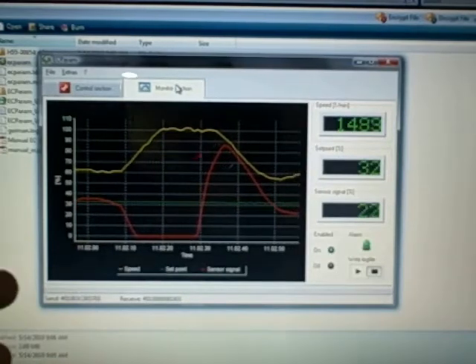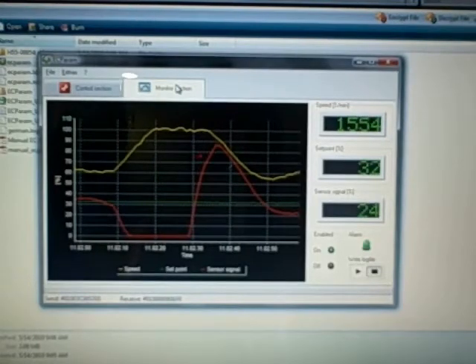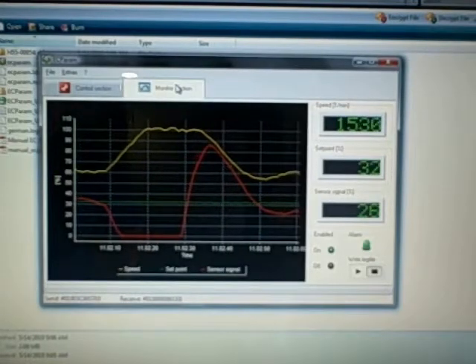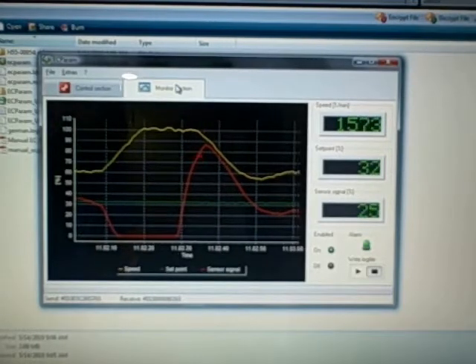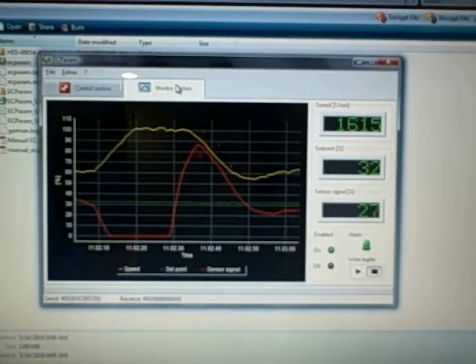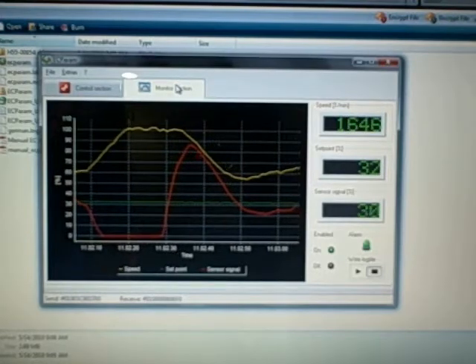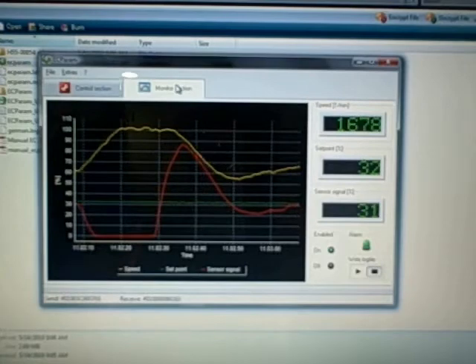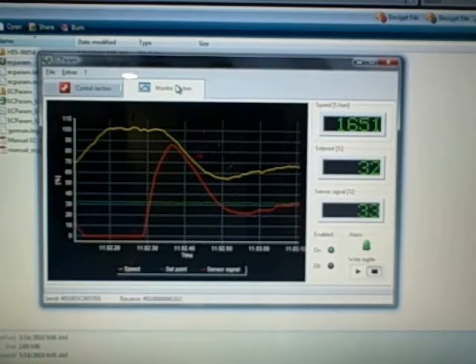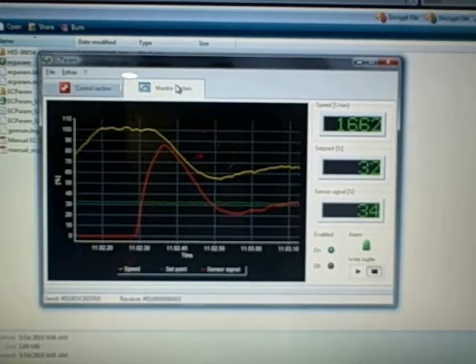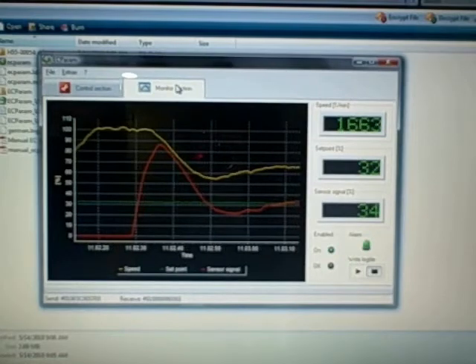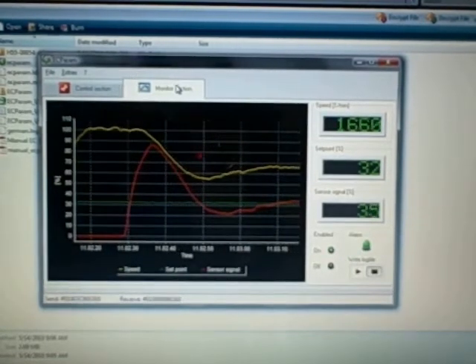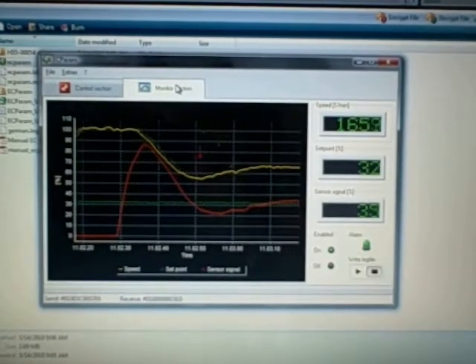And what's nice about this is you'll be able to monitor it remotely. So you can have this computer set up in an office somewhere and have an EC fan in a rooftop system or a VAV box. And you'll be able to tell if your filters are ever dirty so you'll be able to change them in time. You can tell if your coil's dirty.